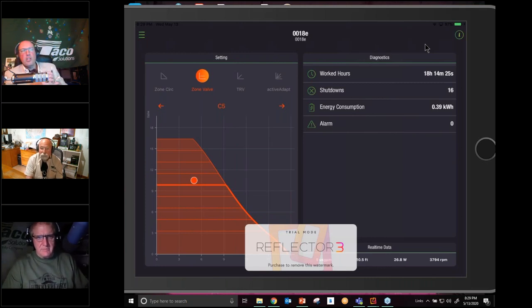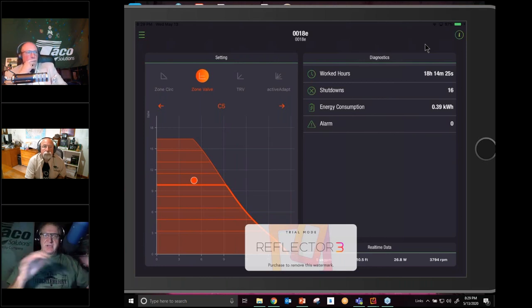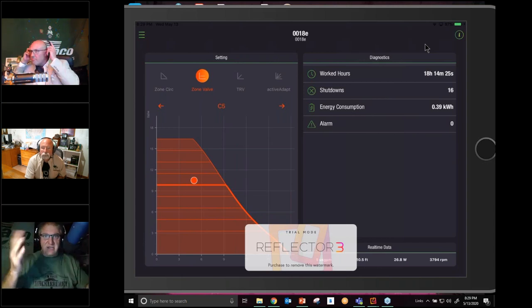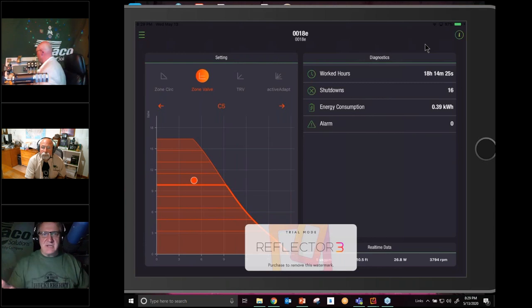There he goes. He says pump location. Yeah. Pump location. We have no recommendations. I mean, you can put the pump on your supply. You can put the pump on the return. Pumping away is always going to be better. If you're ripping out a boiler and you're putting in a new boiler and everything's being rebuilt, pump away from the point of no pressure change where the expansion tank connects to the system. No reason not to. The benefits are many and wide and varied.